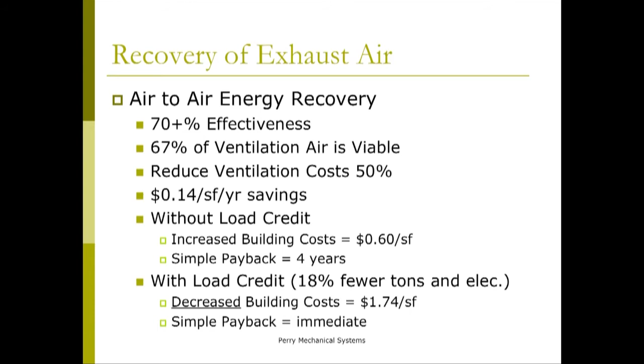So 67% of your ventilation air is a viable candidate for this. When you reduce your ventilation costs by 50%, you're looking at about 14 cents a square foot in savings on your building. Even without considering the benefits of your air conditioning system decreasing in size, you're looking at an increased building cost of about 60 cents per square foot, which comes out to a payback of about 4 years. Now if you take the load credit, since you're recovering this air you can decrease the size of your central plant. That results in 18% less capacity on your overall building tonnage, decreasing your building cost by $1.74 a square foot. So it's an immediate payback, your actual cost goes down by including this technology.